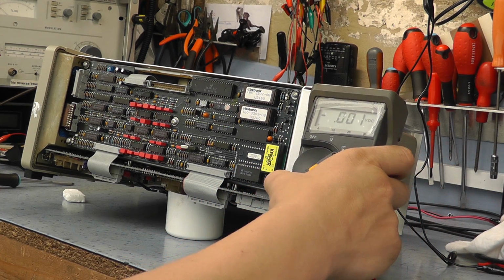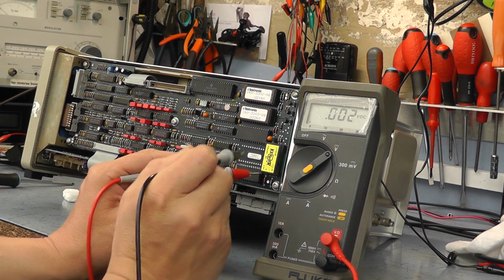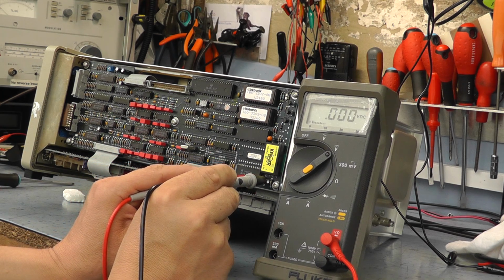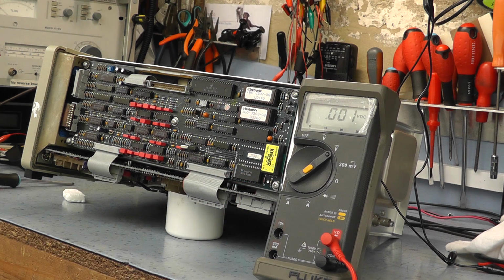Before we get too heavily involved in doing calibration on this scope, one thing I have noticed is if you have a look at the backup battery, it's down to 1.6 volts. Now the scope isn't flagging up anything about this battery being low, but it must be getting close to the point where it will actually record that. Now we know we got an error message on the front screen.